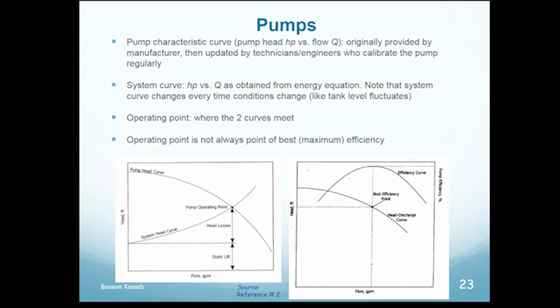But when the tank elevation changes, that system curve is going to change. We're going to have a different curve like that, or a different curve like that. When the Z2 minus Z1 changes, the curve could go down, it could go up, so you get a new operating point. So the operating point is non-unique. So it's not unique. Know that, please. This is only for one case, one study case that I'm showing you. It has one point, but the operating point could be anywhere on the pump curve.